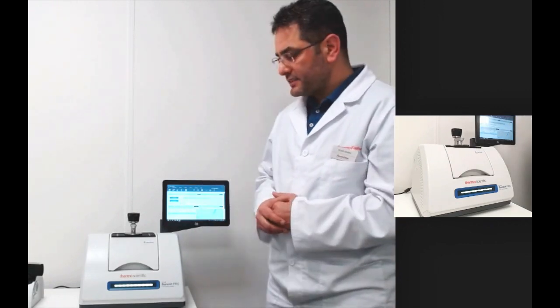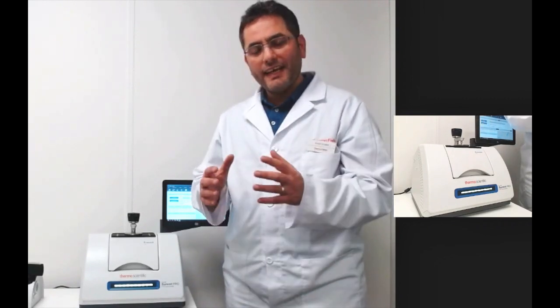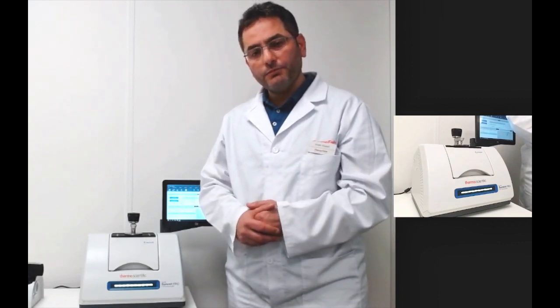The enhanced sensitivity and high signal-to-noise ratio are achieved because we use our large 1.5-inch optics. Such optics maximize the optical throughput, which increases sensitivity and enhances the signal-to-noise ratio. This aspect is very important, especially for a single bounce ATR accessory, since the optical throughput will drop significantly.